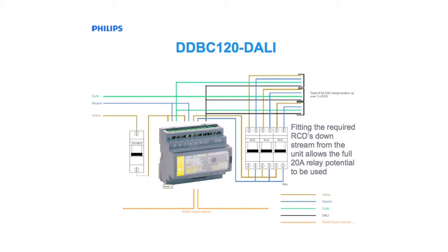Here is a wiring example of how the unit can be connected to circuit protection devices. From the supply, the device is protected by a 20 amp magnetic circuit breaker. This provides protection from overloading on the supply side. As light fittings have an inherent earth leakage current, residual current detection devices have been mounted downstream from the device. Multiple RCDs have been used, which allows for the project to take full advantage of the 20 amp capacity of the internal power relay.